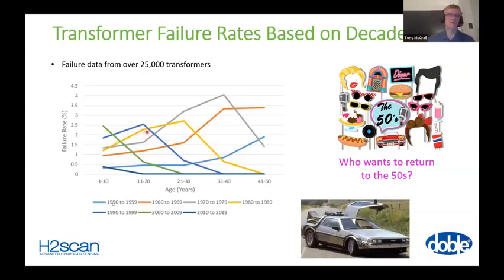But take it for what it's worth, that these are populations, the statistics are for the population. And as ever, we always have to remember the statistics apply to the population and not the individual. So if I have a transformer from 1985, say, to work out what condition it's in, I have to go and look at that individual transformer. I have to go test and assess, gather the data, make decisions, analyze, work out what failure modes may be in operation, and then work out what the urgency of my intervention might be and how long I think this unit has. Likewise, if I have one from 1990 to 1999, I may expect the population to show that some of them will likely fail sooner, but to find out about an individual unit, I need to look at that individual unit. And that, to me, is the important message. Statistics are applying to the population, not to the individual.